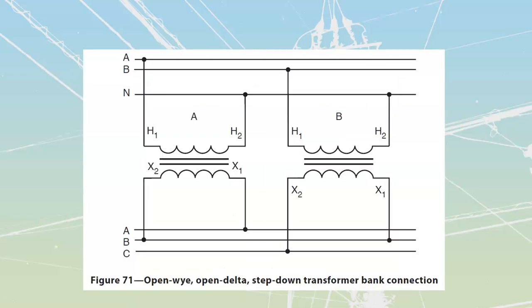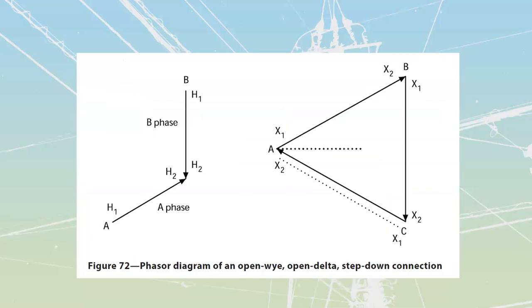The last connection we're going to look at is what they refer to as an open Y, open delta. This is what the open Y, open delta looks like. The primary is connected as an open Y, and the secondary is connected as an open delta.